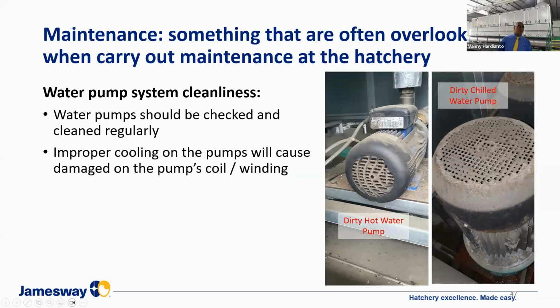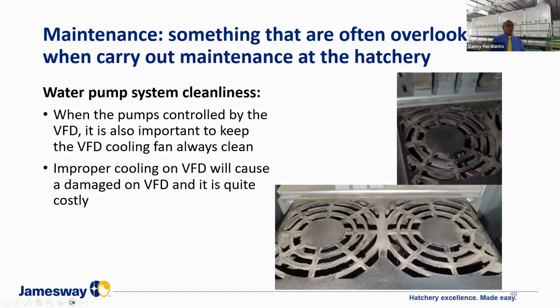The water pump should be checked and cleaned regularly. Improper cooling on the pump will damage the coil or the winding inside. When the pumps are controlled by a variable frequency drive, it is also important to keep the cooling fan always clean, because improper cooling on the VFD will cause damage to the VFD itself, and it's quite costly.